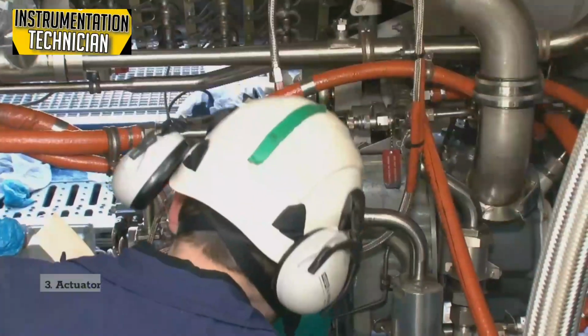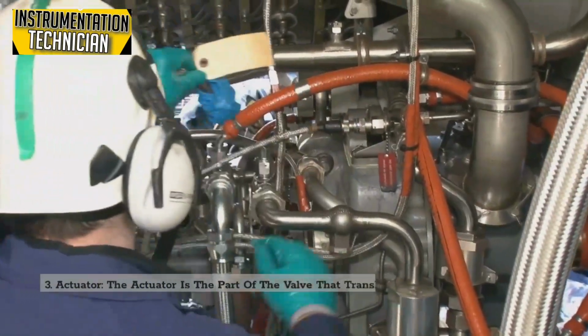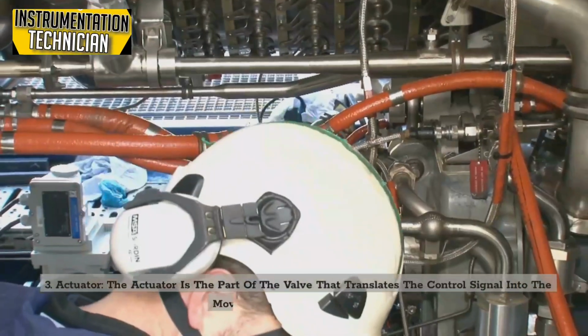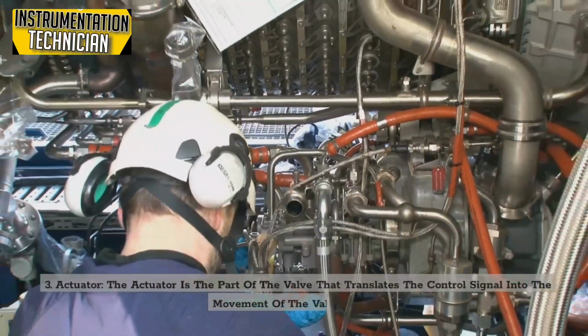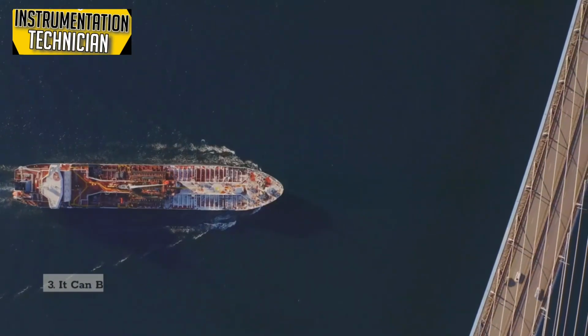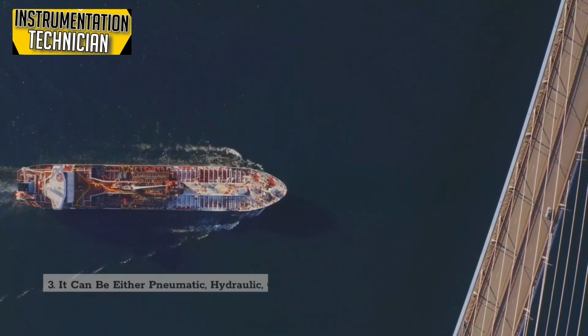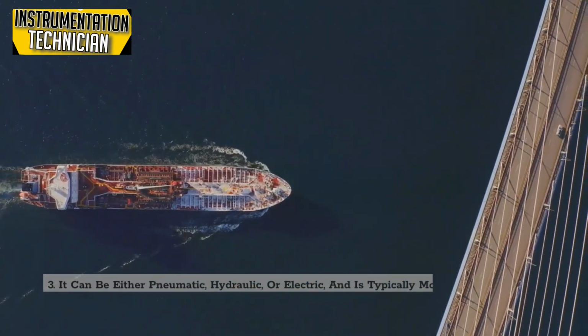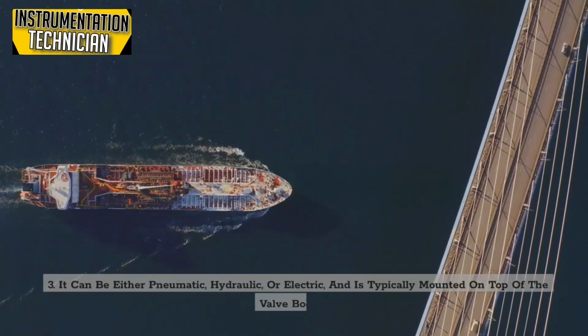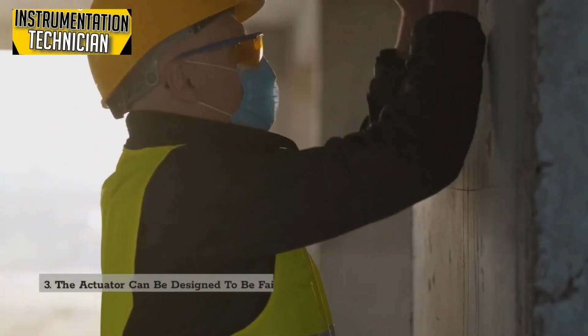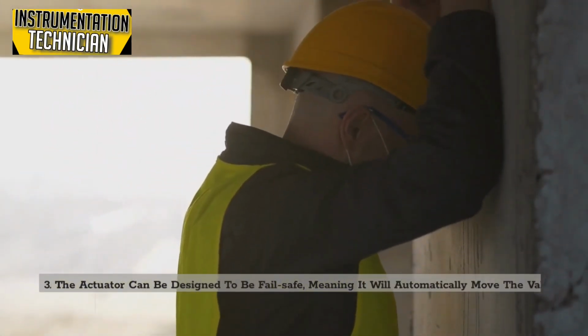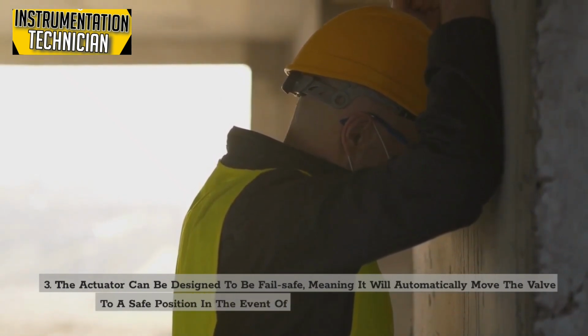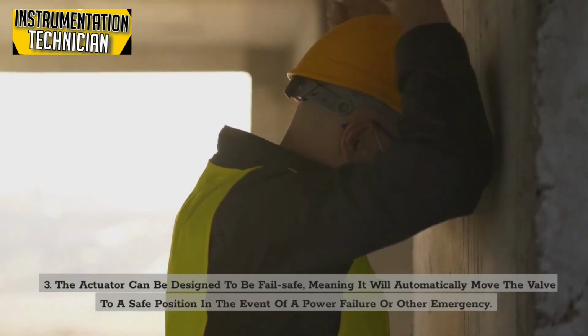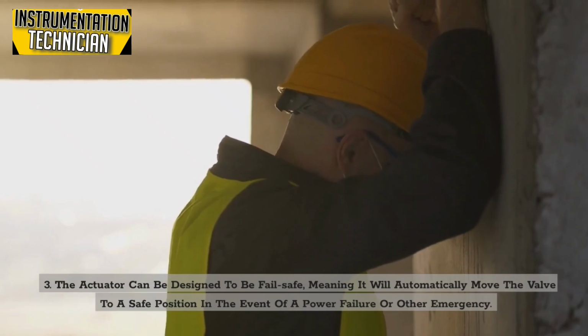conditions. 3. Actuator. The actuator is the part of the valve that translates the control signal into the movement of the valve plug. It can be either pneumatic, hydraulic, or electric, and is typically mounted on top of the valve body. The actuator can be designed to be fail-safe, meaning it will automatically move the valve to a safe position in the event of a power failure or other emergency.